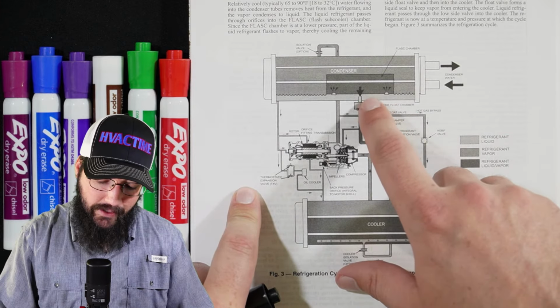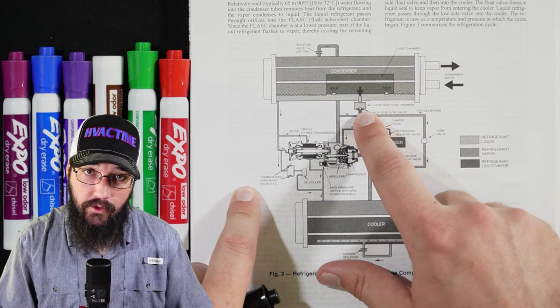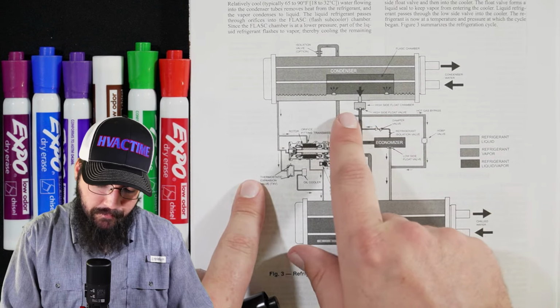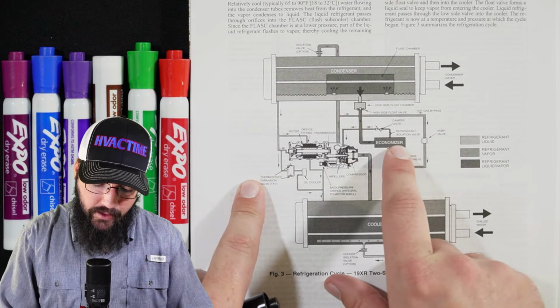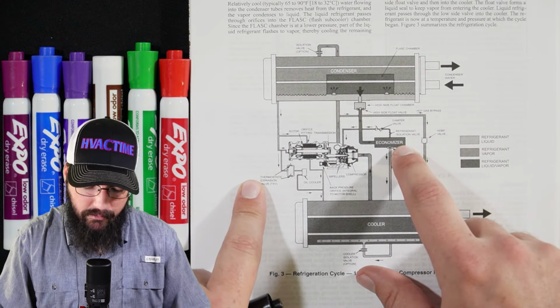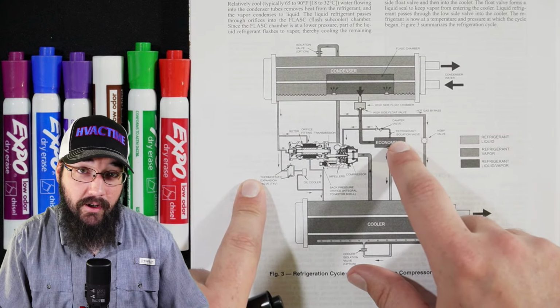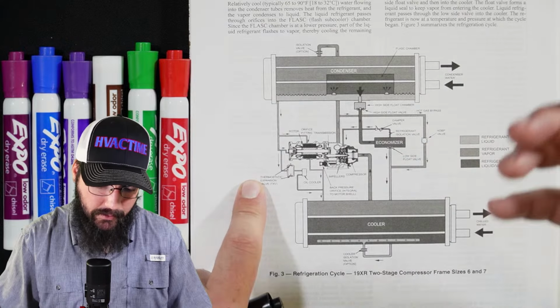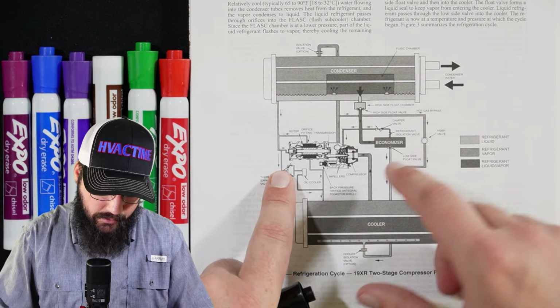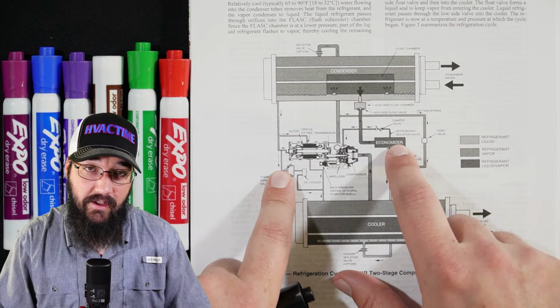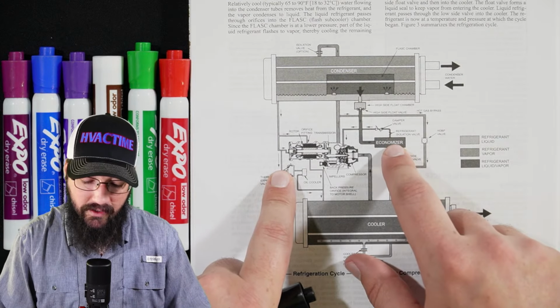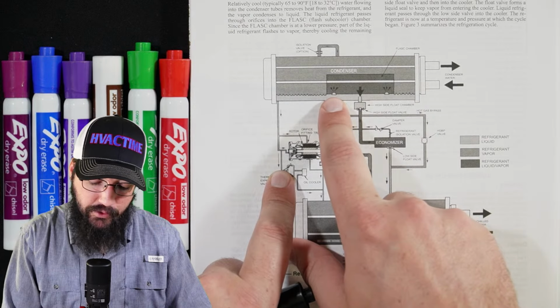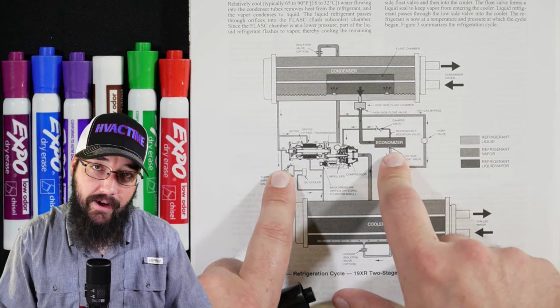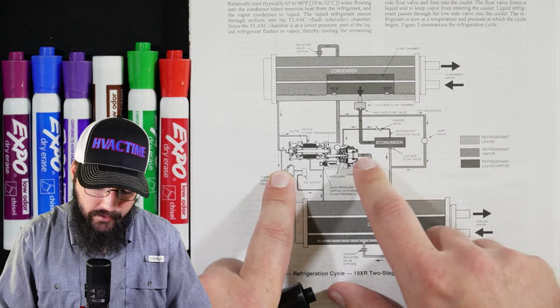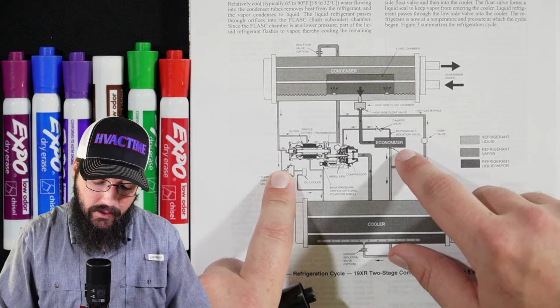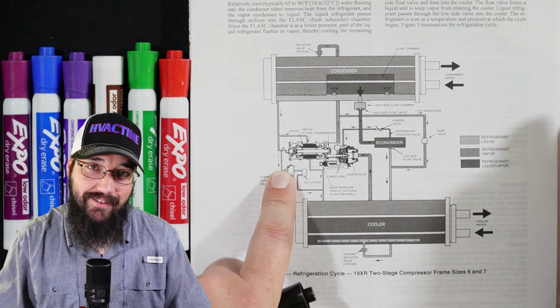Ultimately, as it drains down, we process through our float valve, and I'll go deeper into the float valve in just a minute. But we flow through the float valve. This particular one comes into our flash tank economizer. So this would be our second stage economizer. That would be a realistic way to look at this, in my opinion. Some people may argue that. My opinion is I would look at this as a second stage economizer, this being first stage, this being second stage. And this would be your first stage flash, second stage flash, final metering device going into the evaporator. That's how I would personally lay this out, and looking at it just from design principles, right?